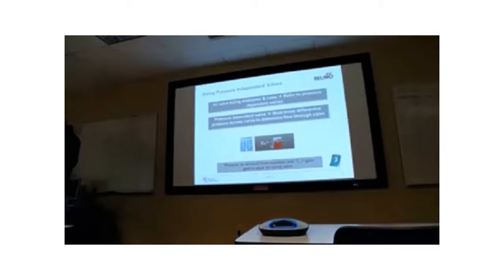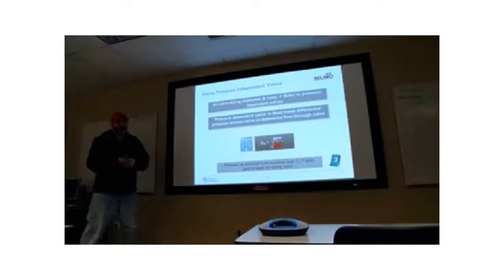So if you had to pick a valve, say your coil is 10 GPM or 15 GPM, you can go into our catalog and pick a valve that flows at a design flow of 15 GPM, or you can adjust it to that. That's the way you pick them. So that's the easy button as far as picking.